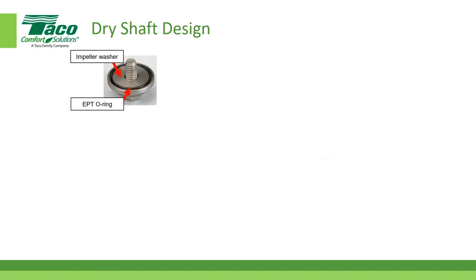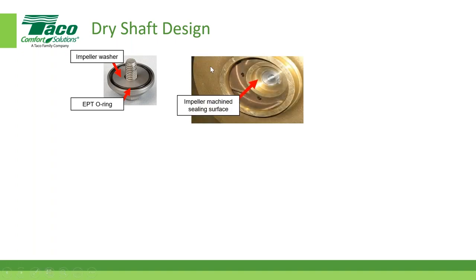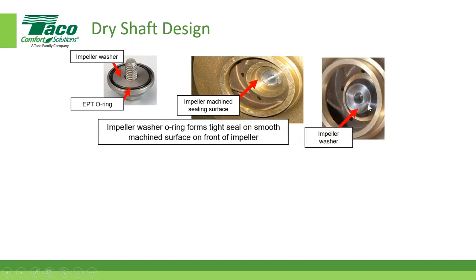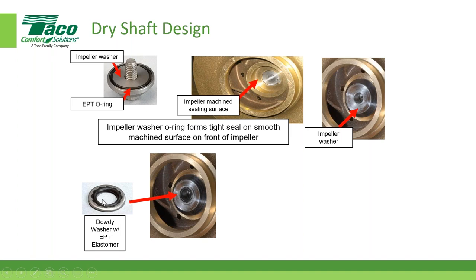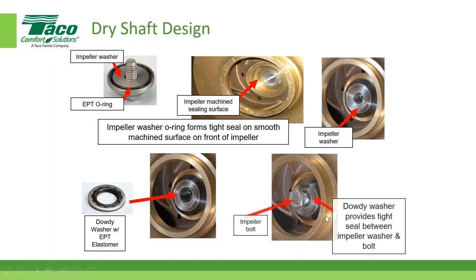And anytime you're working on pumps and you start taking things apart, I always recommend replacing O-rings with new ones. Sometimes they get pinched during removal or putting together. So I just recommend you replace them. You can see that machined sealing surface right there, where that piece goes in to mount that impeller. There's an impeller washer there. So that forms a tight seal on that smooth machined surface on the front of the impeller. And there's a Dowdy washer, and that's another component that I personally recommend that you replace. If you have to take those apart and put them back together, they can get compromised very quickly, and then you're going to have some issues, potentially. So something to consider. And then there's that impeller bolt, and the Dowdy washer provides a tight seal between them.